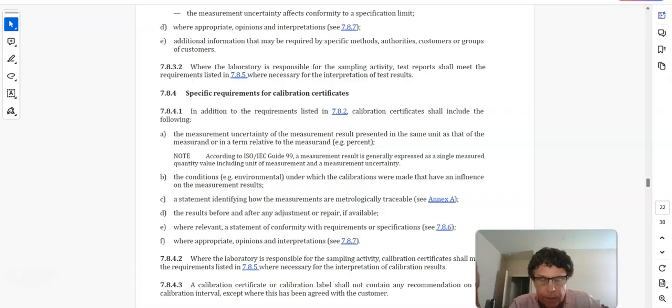If you have pipettes and they're not calibrated, you will get a nonconformance. If you have timers that are measurement results and they are not calibrated, you will get a nonconformance. If you have a calibration certificate for a measurement device and it's not by a competent provider, you will get a nonconformance. So don't be surprised when you get one, or say you didn't know because you watched my video.